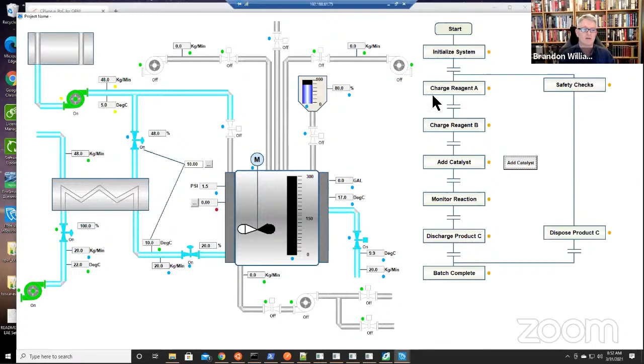Is there a way to automate commissioning after deployment? You mean like commissioning of a whole industrial plant? I assume, what John walked through, with a control system physically in place but no software running, to it actually running, and then opening valves and turning on pumps. Operators wouldn't do that manually. This is an industrial system, but just showing that a 50 or 100-hour step-by-step process can be reduced to 10 minutes is really meant to show the power of orchestration throughout the entire life cycle of running that plant.